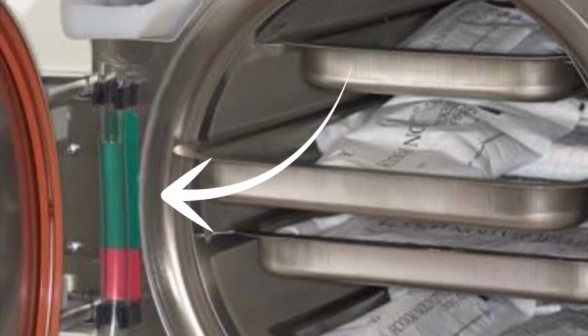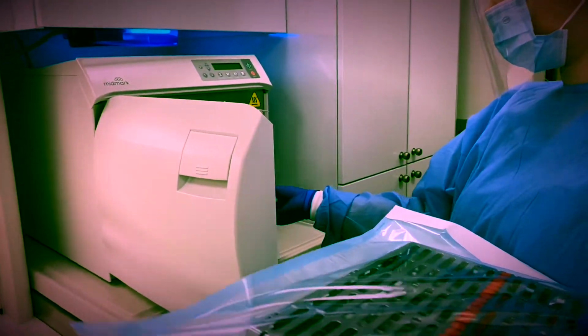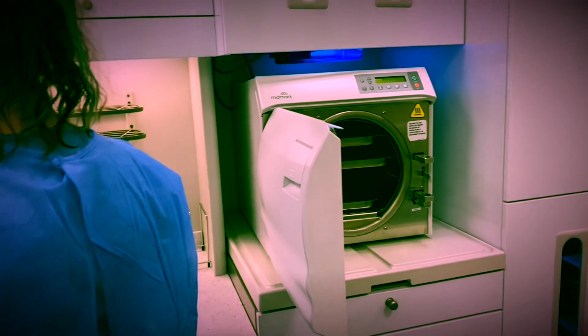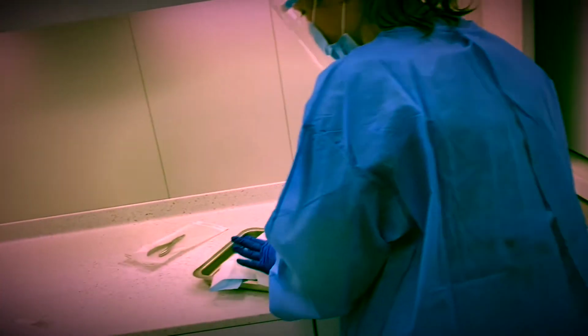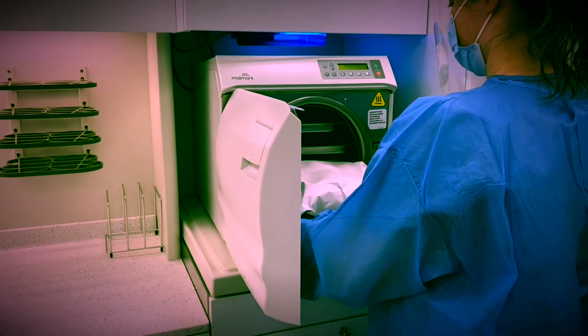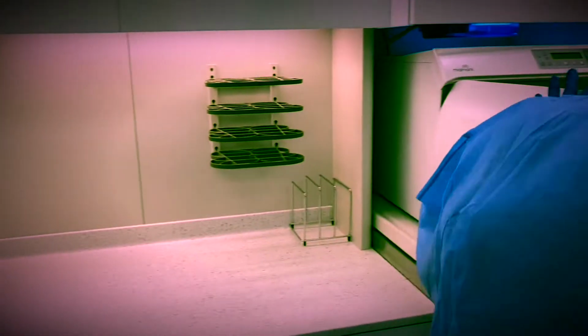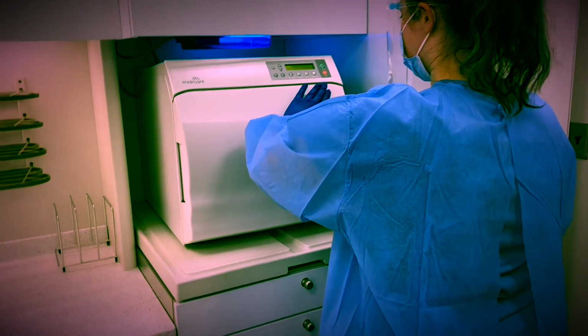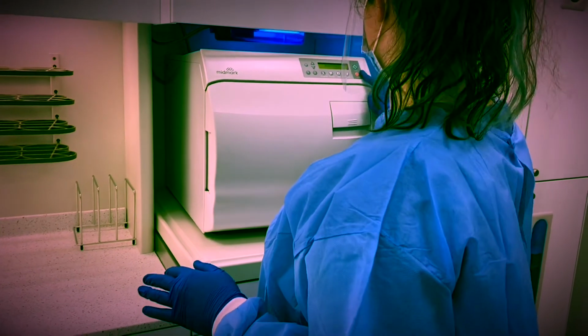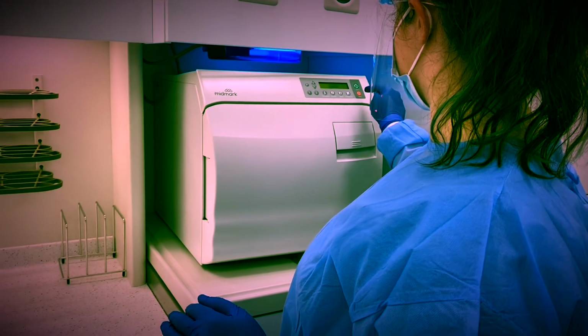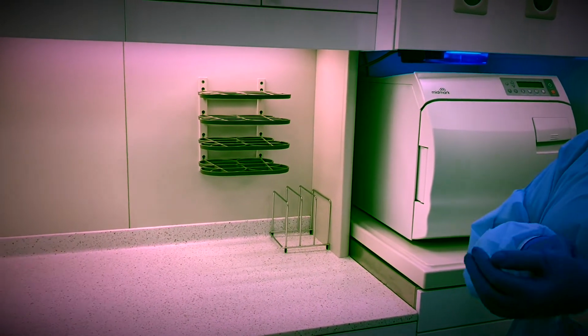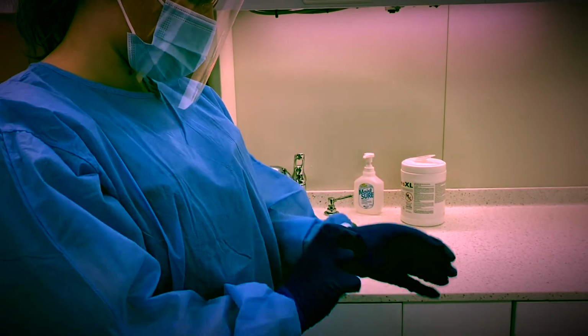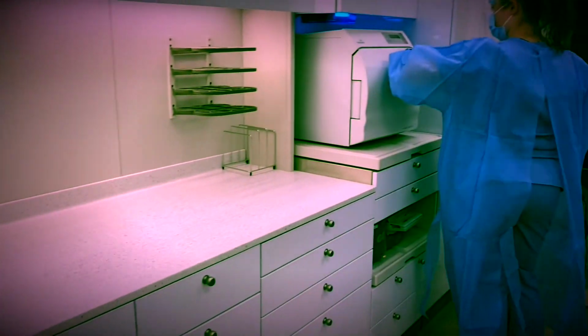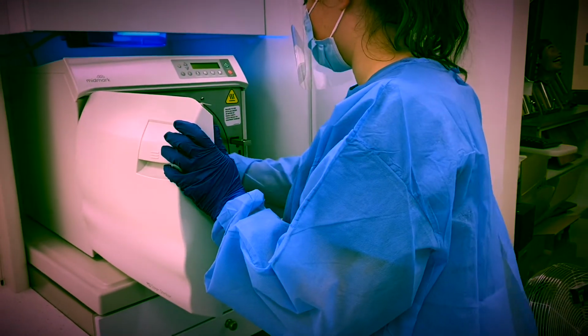The water level for the autoclave must be checked frequently as well, and filled to the appropriate level. You cannot stack packages on top of each other in the autoclave. The autoclave will either have shelves or racks. This autoclave has shelves with holes so the packages will be able to go on each shelf. When the autoclave is done with its cycle, it will automatically open on its own, alerting you that it is done.